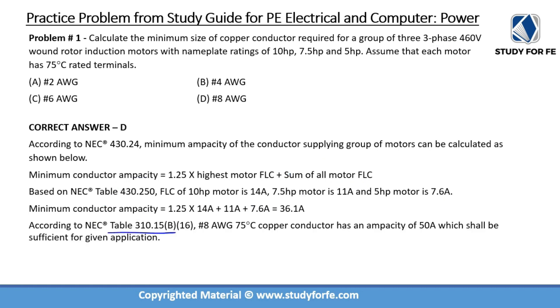According to NEC table 310.15(B)(16) — the table we discussed during conductor sizing — we look at the 75-degree-rated column and need a copper conductor. A number 8 AWG copper conductor with 75-degree C rated insulation has an ampacity of 50 amps, which is sufficient for this application. Going any lower would not satisfy the 36.1-amp requirement.